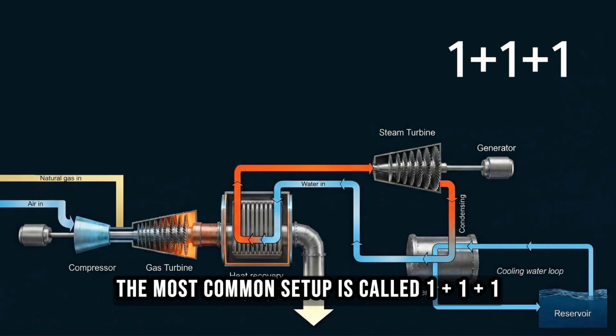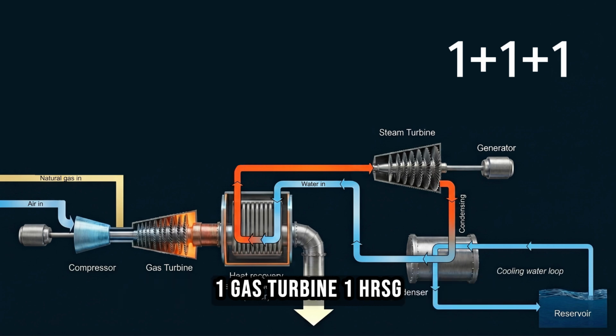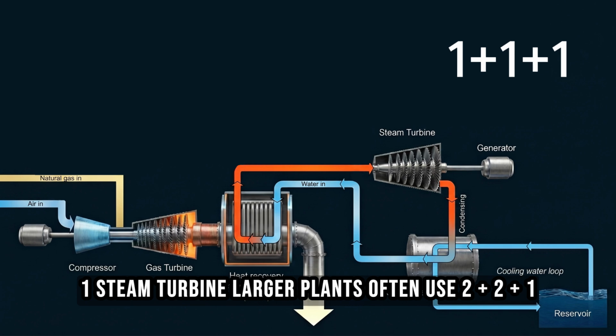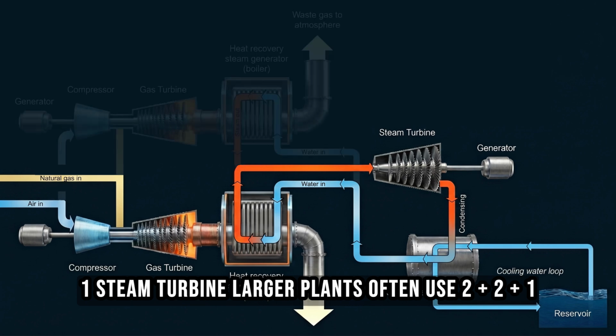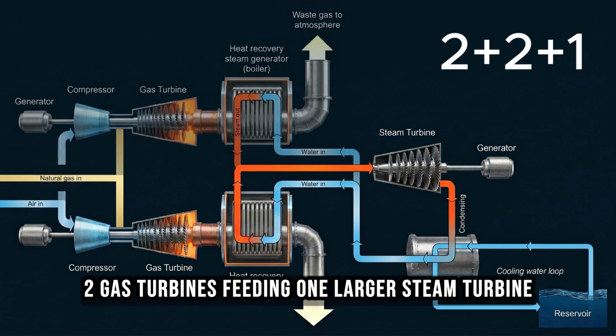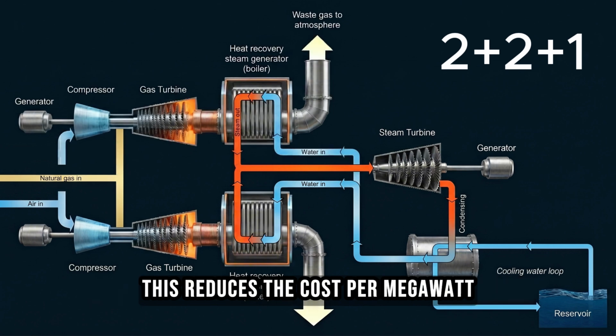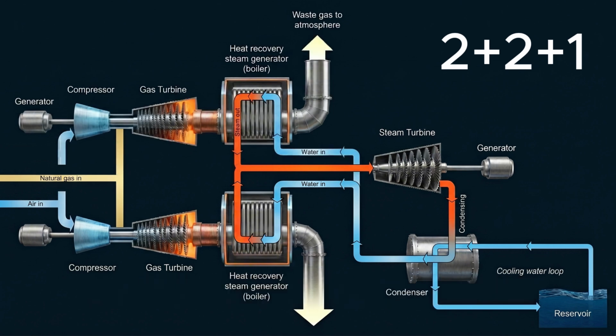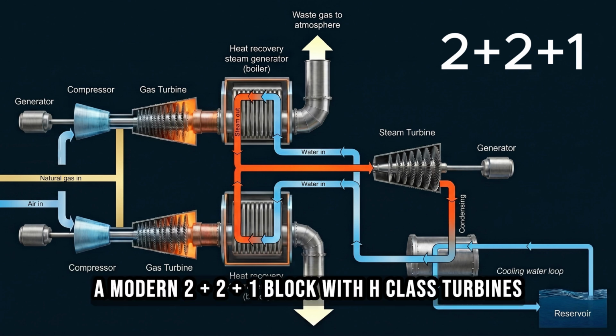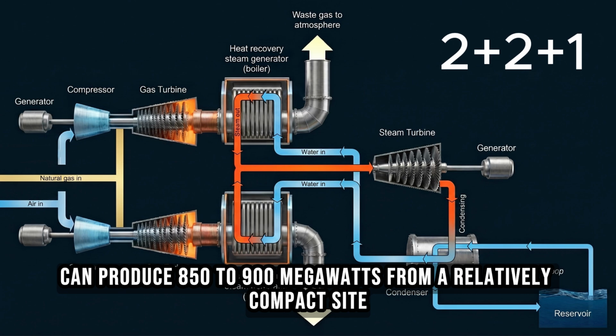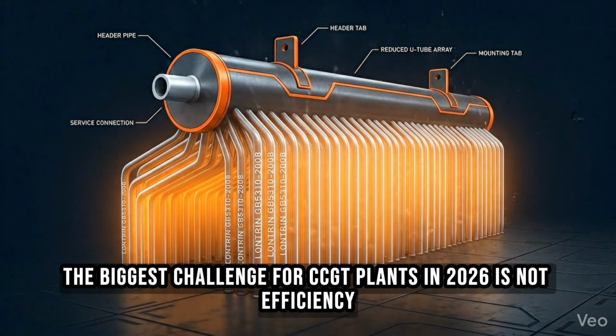The most common setup is called 1 + 1 + 1. 1 gas turbine, 1 HRSG, 1 steam turbine. Larger plants often use 2 + 2 + 1, 2 gas turbines feeding 1 larger steam turbine. This reduces the cost per megawatt. A modern 2 + 2 + 1 block with H-class turbines can produce 850 to 900 megawatts from a relatively compact site. The biggest challenge for CCGT plants in 2026 is not efficiency, it's daily cycling.